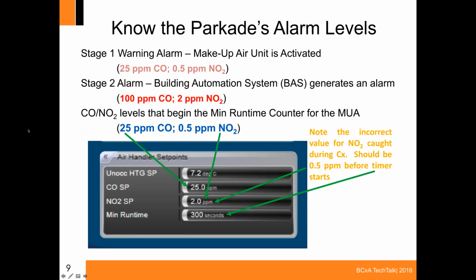So this screenshot here about the Parkade alarm levels, it's important to know what you need to do for your building. The stage 1 is 25 parts per million of CO, as I mentioned, and 0.5 parts per million of NO2. And what that triggers is your ventilation equipment would actually come on. This screenshot right here is from the building automation system and shows that at 25, this is when our ventilation system would begin a countdown timer to actually shut down. So we've gone up above the 25, activated the ventilation unit, then once it comes back down below 25, for 5 more minutes that unit will run to bring in fresh air.